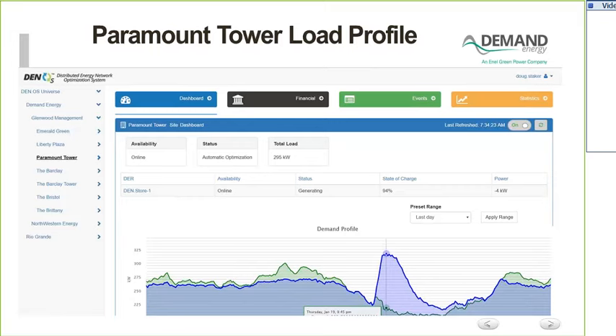If it's AC coupled, we can always feed something in. If the battery's full, we can use it as direct load, and it's just as easy - no more efficient, but we can load follow. We monitor by letting it be AC coupled and affect the load in the building, and our metering just watches the load of the building, and that's how we respond. So it's probably easier to control AC coupled than DC coupled.